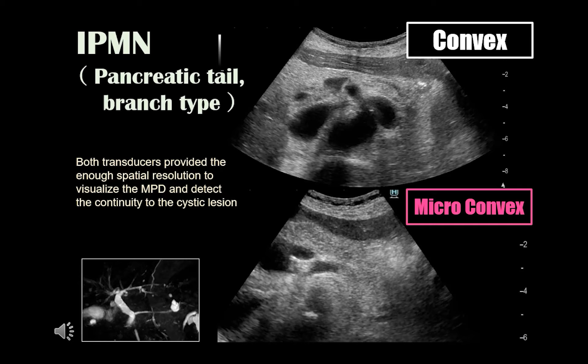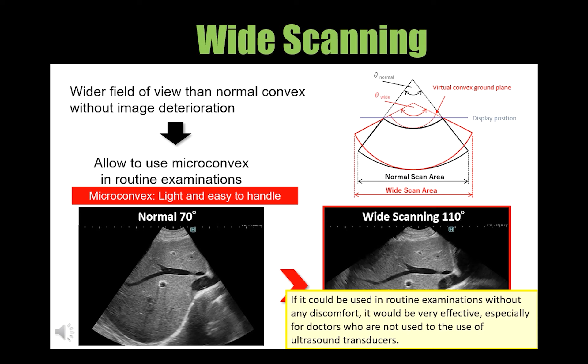Next, let me introduce a new function, wide scanning. Wide scanning is a function that provides a field of view equivalent to that of a regular convex probe by widening the view angle to 110 degrees, while minimizing image quality deterioration. As a result, this microconvex probe is not only light, but also very easy to handle. If it could be used in routine examinations without any discomfort, it would be very effective, especially for doctors who are not used to the use of ultrasound probes.